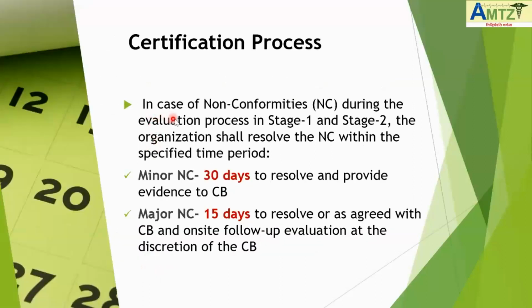In case of non-conformities, we have some duration. Minor non-conformities, maybe one instrument was not calibrated but was still used, or a small flaw in the washing, a minor one which is basically a one-time occurrence. They are given 30 days. A major non-conformity is where you're not following a procedure, or you're doing something which directly affects the quality of your results. Or you have a procedure, you have something in black and white, but you are not following it. These come under major non-conformities, where normally there is a follow-up evaluation and a 15-day period is given. So that is how it is. Yeah, next.